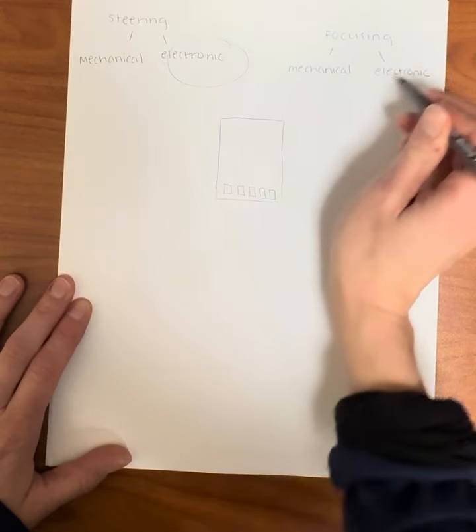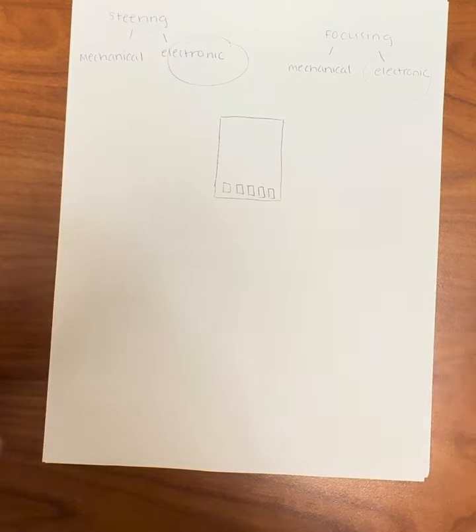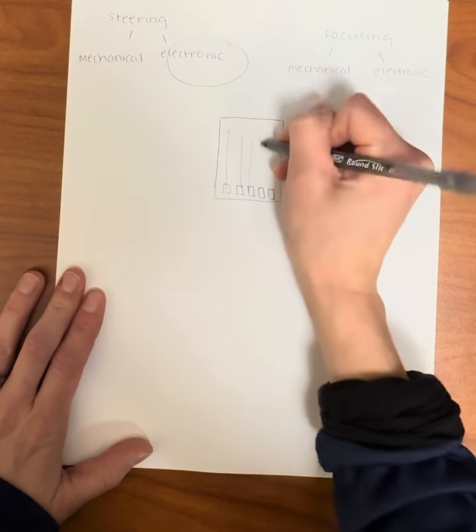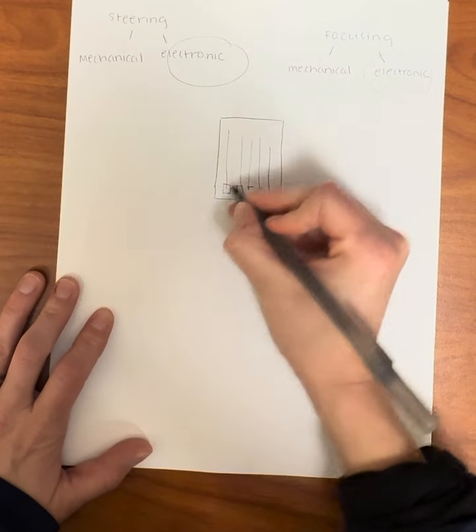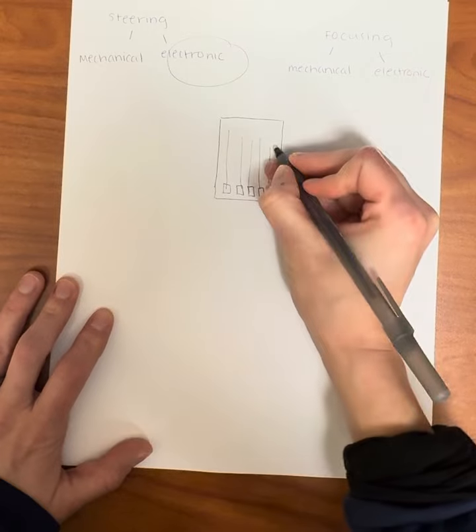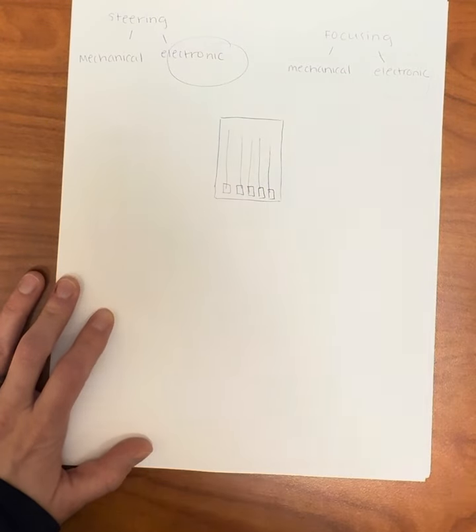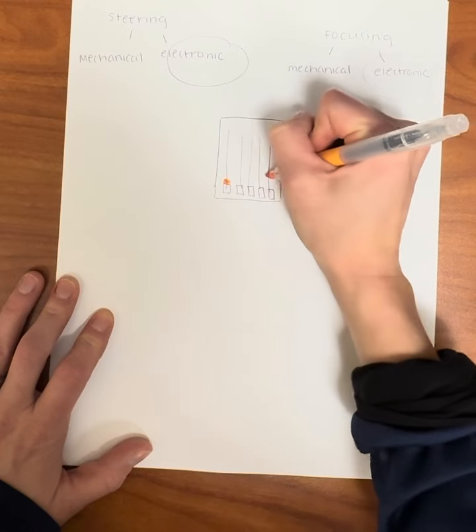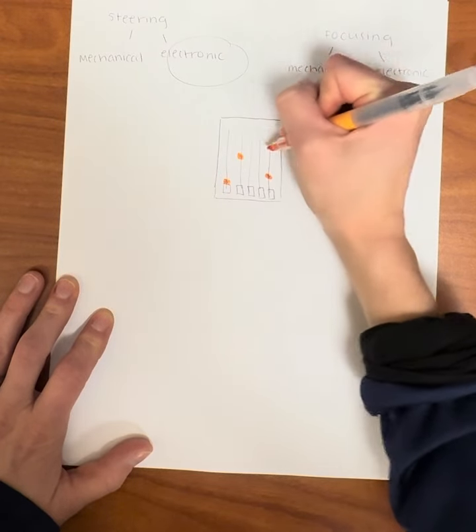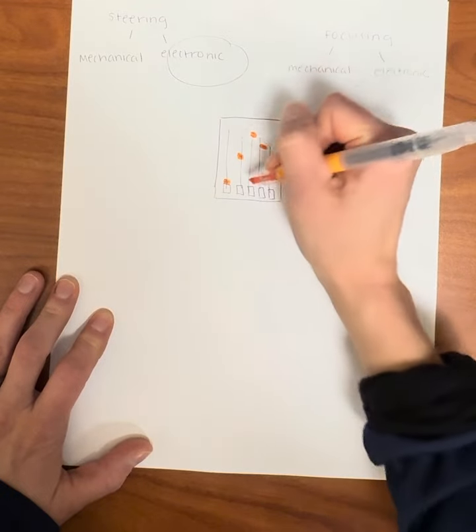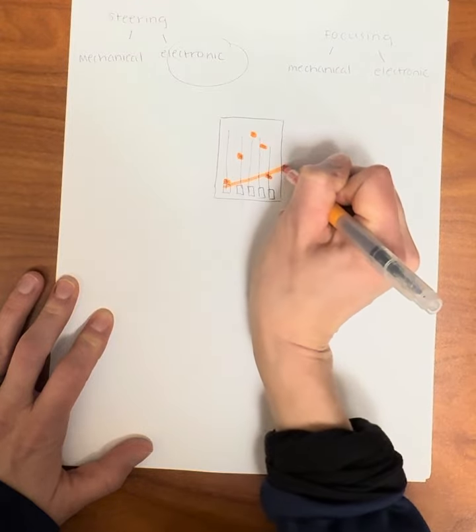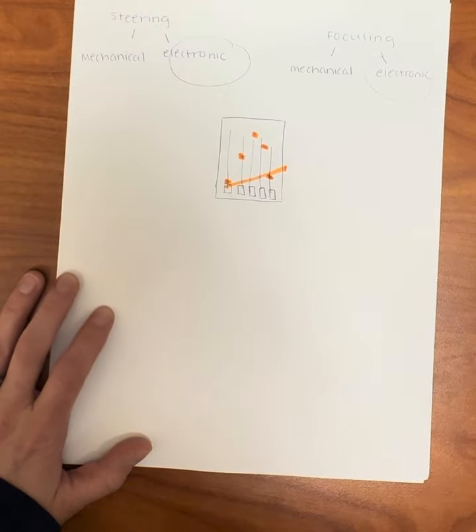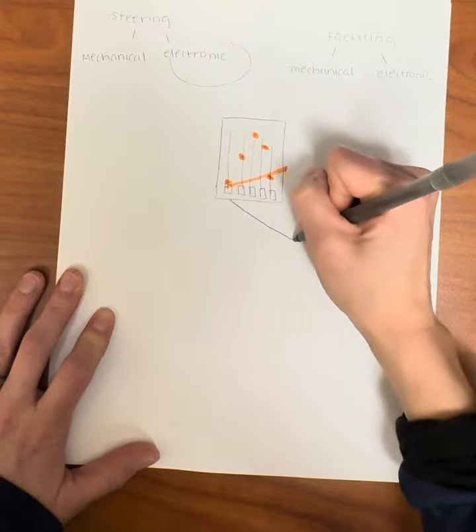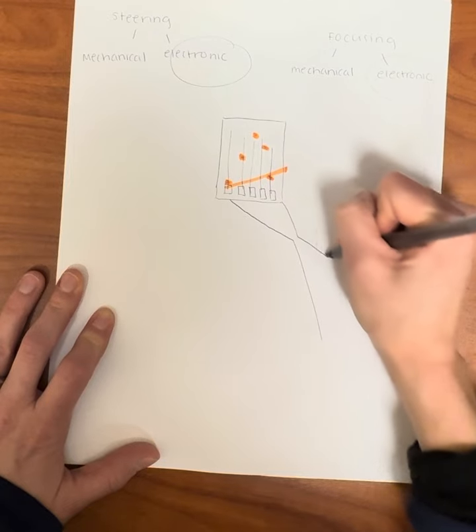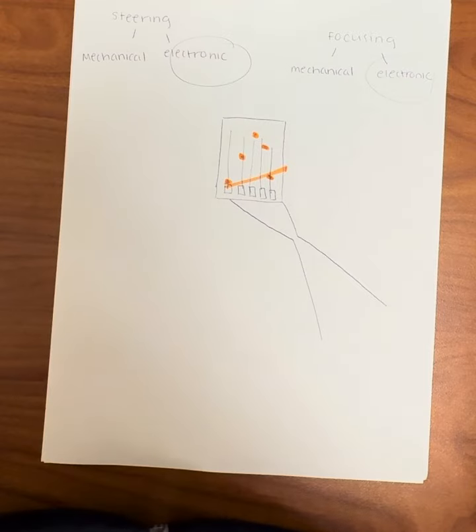So now these can be combined, right? We can electronically steer and electronically focus at the same time with phasing. And what that might look like is that we will delay our timing on an angle, but also in a curved pattern. So we would do here and then here and then here, and then here, and then here, and we still get a curved pattern but on a slight angle. And when we do that, we wind up with a beam that both focuses and steers at the same time by using phasing.